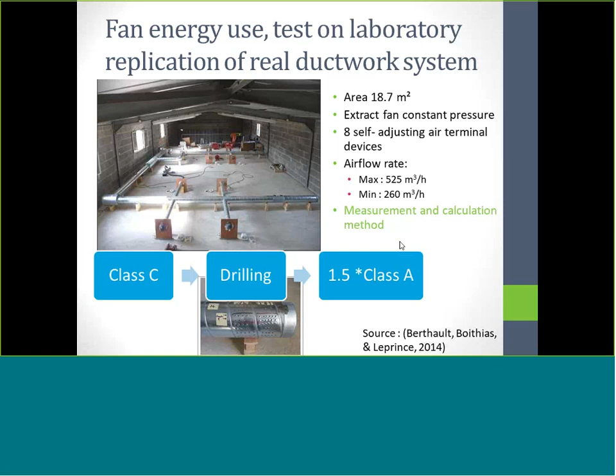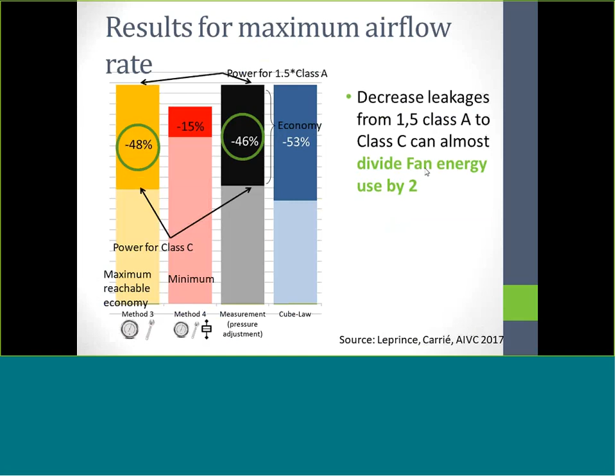What we found out is that with the measurements, going from a not airtight ductwork at all to a tight ductwork will decrease the fan energy use by 46%. This was done by measurements, and with our calculation method, we obtained 48%, so more or less the same. Which means that by having an airtight ductwork, we can divide the fan energy use almost by 2. And this is not the only study that has shown something like that.